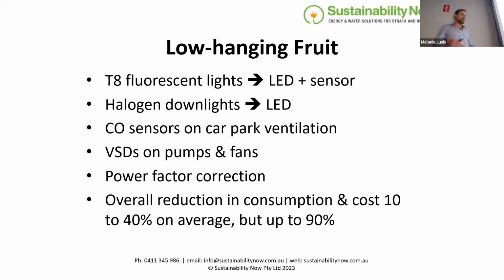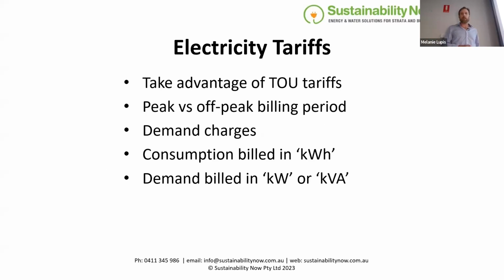And a power factor correction unit's a very simple thing. It's just a capacitor bank that sits on your main switchboard and basically lowers your reactive power, so the ratio of kilowatts to kVA is close to 1. But I regularly see overall reduction in consumption and costs between 10 and 40%. 90% doesn't happen very often, but quite regularly 40% savings we can achieve.